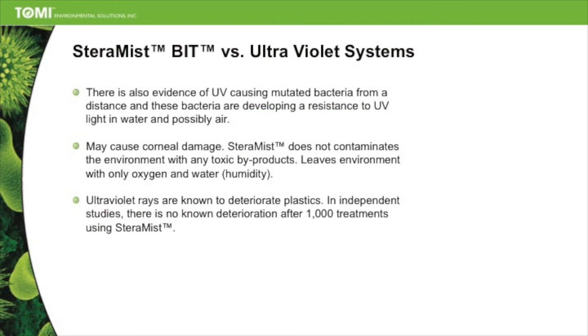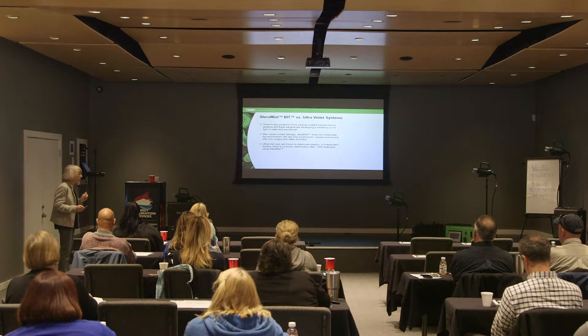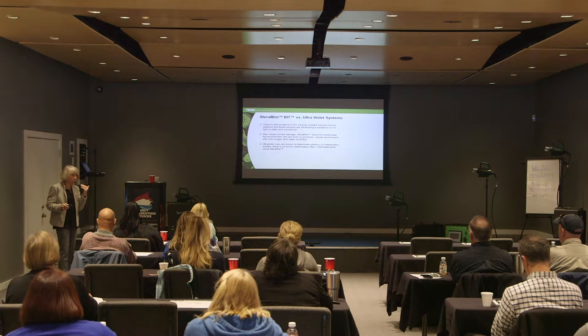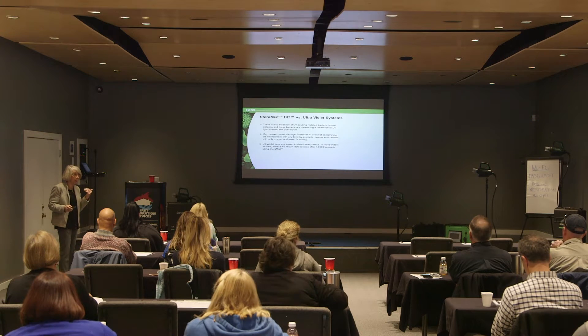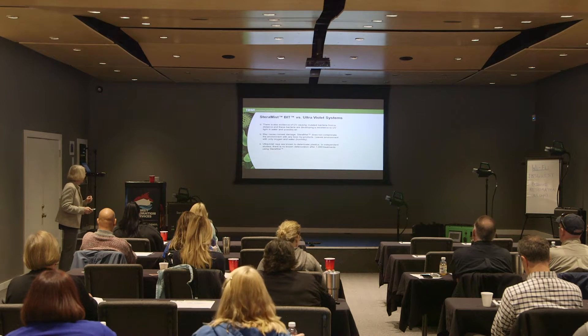There's some evidence that bacteria can be mutated by the use of UVC, and that there is some resistance to UV in light and in water — UV is sometimes used to disinfect water in water systems. UV may also cause damage to the user, such as corneal damage, if you don't wear appropriate protective equipment. That's why most machines have a fail-safe stop so they're not emitting.